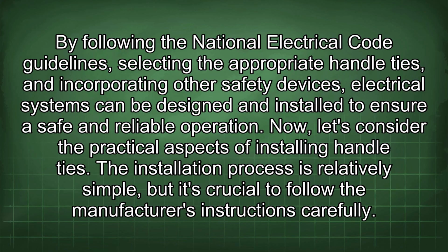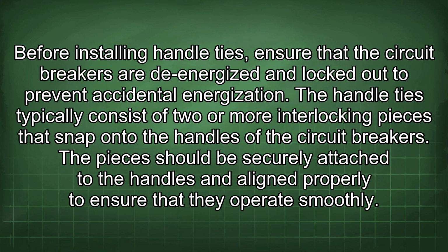Now, let's consider the practical aspects of installing handle ties. The installation process is relatively simple, but it's crucial to follow the manufacturer's instructions carefully. Before installing handle ties, ensure that the circuit breakers are de-energized and locked out to prevent accidental energization. The handle ties typically consist of 2 or more interlocking pieces that snap onto the handles of the circuit breakers. The pieces should be securely attached to the handles and aligned properly to ensure that they operate smoothly.